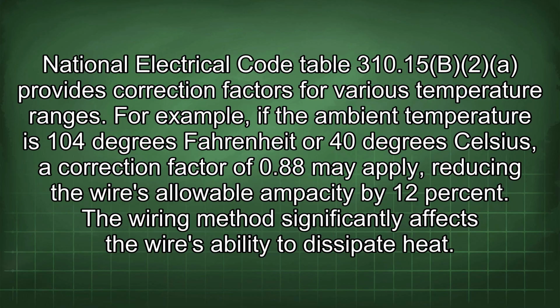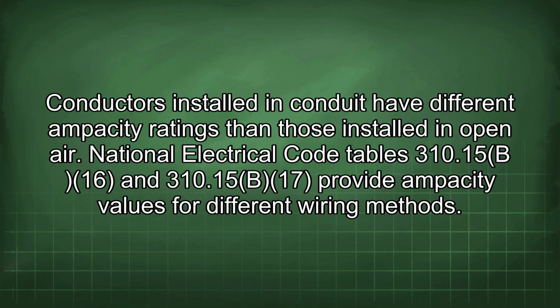The wiring method significantly affects the wire's ability to dissipate heat. Conductors installed in conduit have different ampacity ratings than those installed in open air.